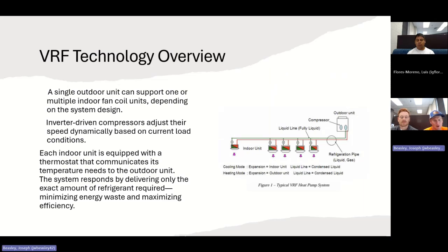Basically, the overview of this system is a single outdoor unit that is the compressor, and it compresses the refrigerant and sends it through the lines to each individual indoor unit where a fan coil is. Depending on the load that each unit needs, it adjusts the refrigerant going through the fan coil to basically change the temperature of the air that is going through the system.